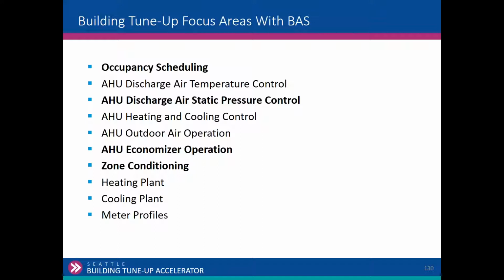So when we look at the focus areas with BAS, I mentioned scheduling. Discharge air static pressure control, that's central station air handlers with VAV. So what's that set point? Is it adequate? Is it too high? Is it too low? Economizer. We all talked about economizer before. We have a lot of economizer hours in our climate. So is the economizer working? What are the set points for the economizer? There's a variety of reasons for overriding those set points, but is the economizer functioning? Is it using an appropriate set point?